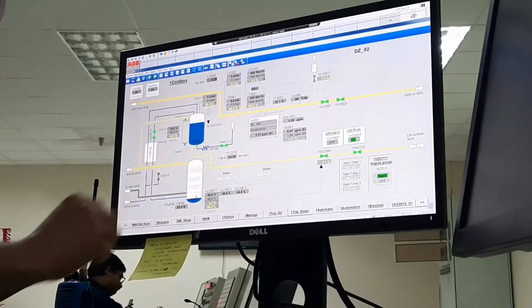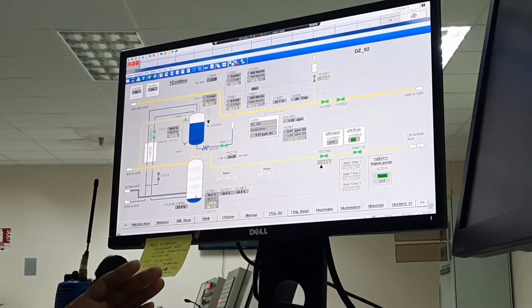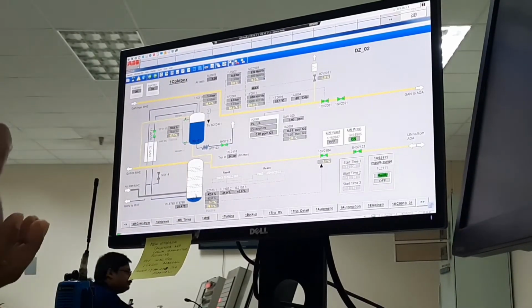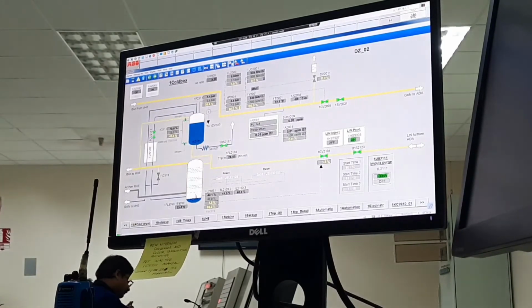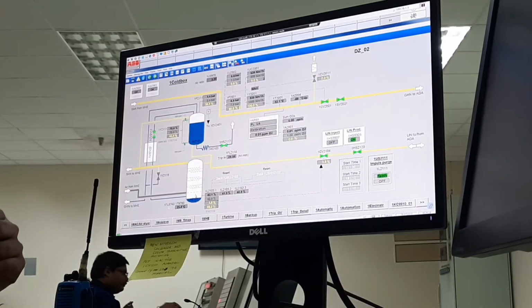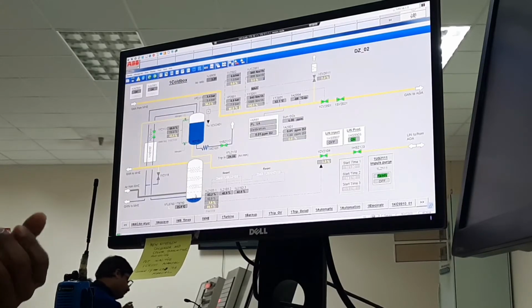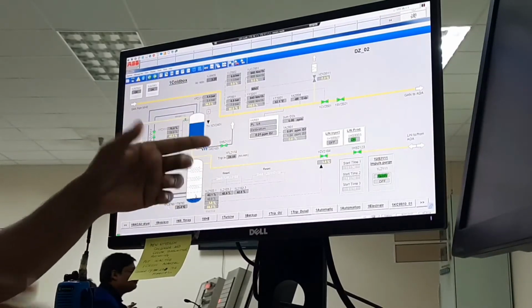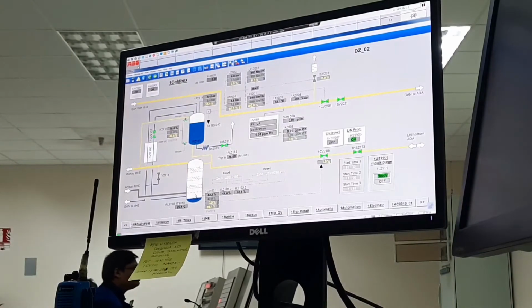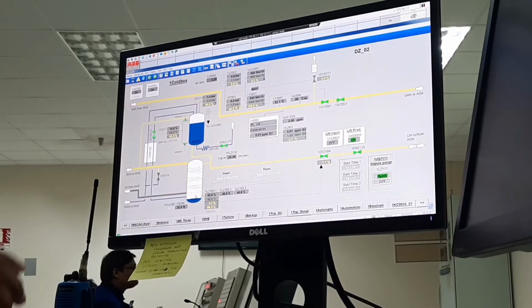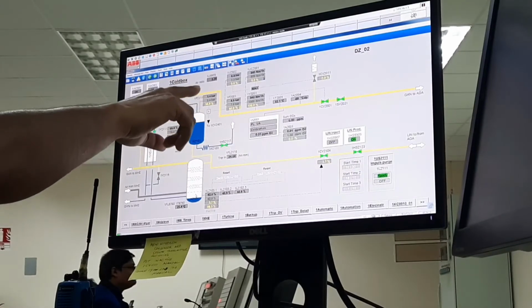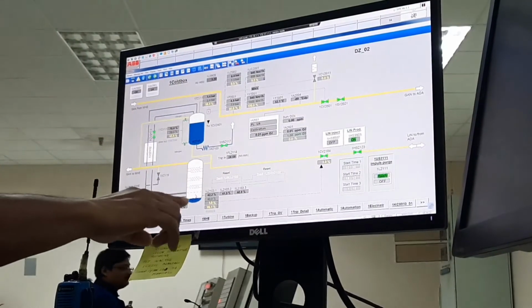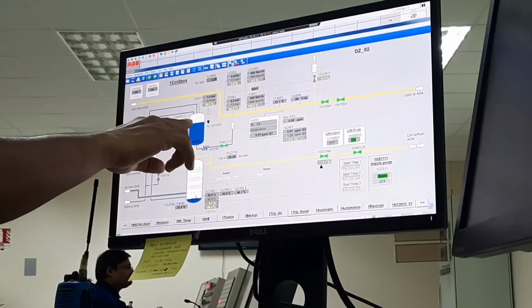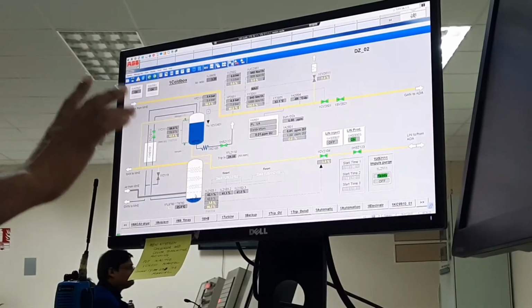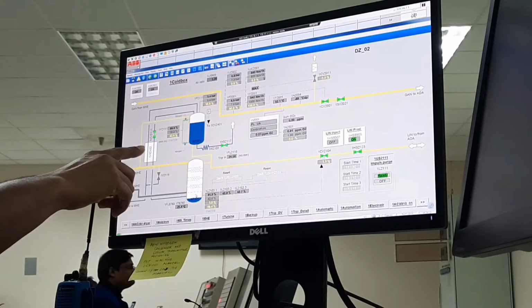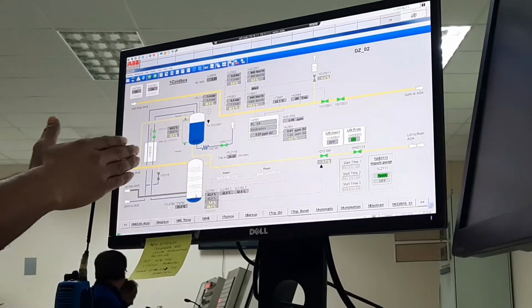If rectifier column pressure is low and condenser pressure is high, it is not possible to go to the condenser, because the receiving vessel must be at lower pressure than the sending vessel. Like the nitrogen tank pressure we are maintaining 5.3 kg and this nitrogen 6.9, around 7 kg. Clear or not? So for that reason we are maintaining this vessel pressure at 3.4 kg. If pressure is more than 3.4 kg, this product will go by gravity to the condenser. But before going to the condenser, it will go through the liquefier. Why will it go to the liquefier?